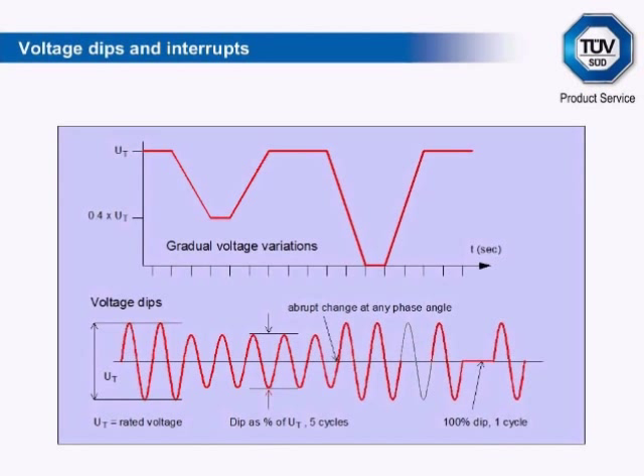The basic parameters are interruptions to 0% voltage from half a cycle to 50 cycles — a dip down to 0 volts lasting from half of one power cycle (one half of 1/50th of a second) right up to one second (50 cycles). And dips from 40% to 70% of the nominal voltage, from half a cycle to 50 cycles — so dipping down to 40% or 70% of the normal power supply.